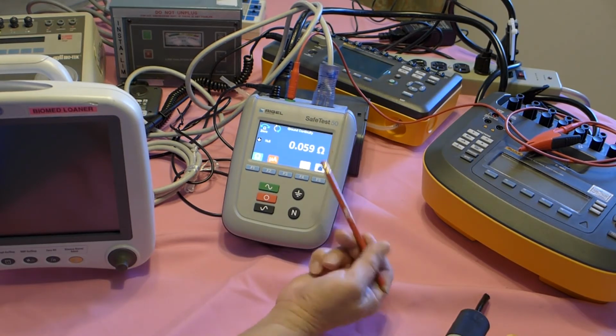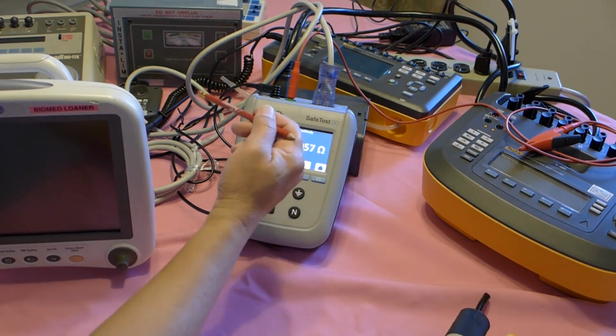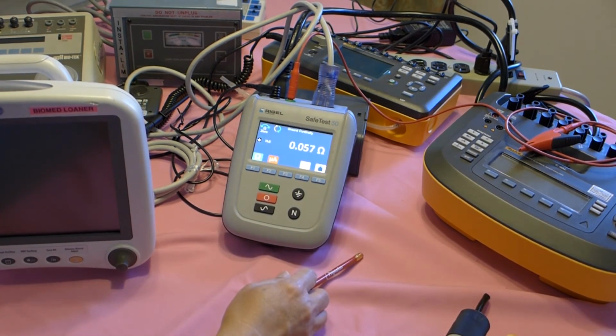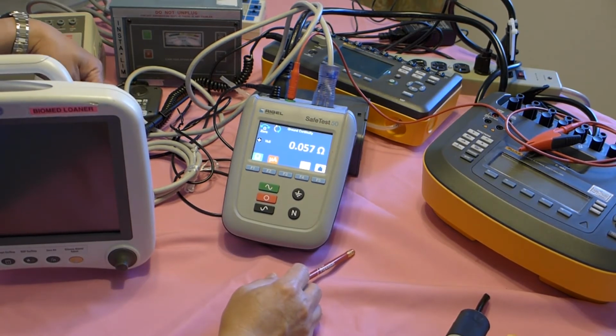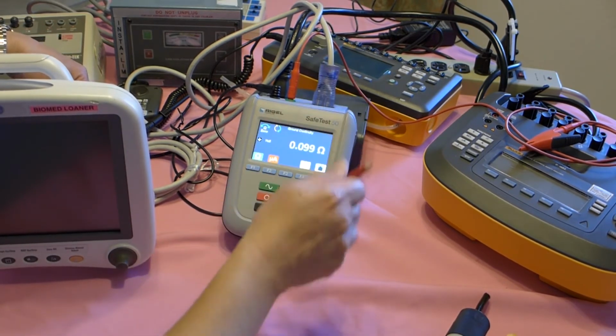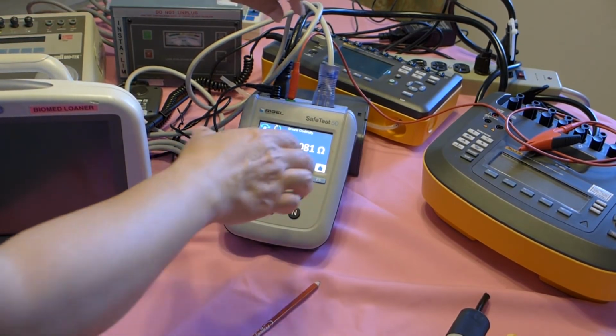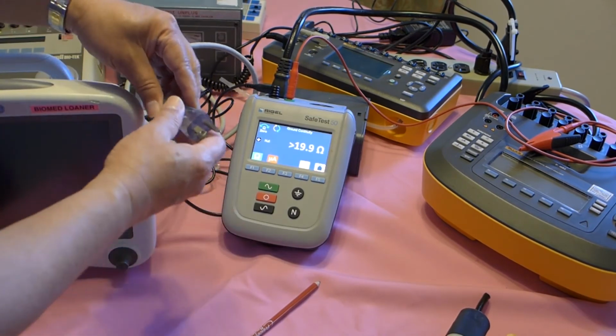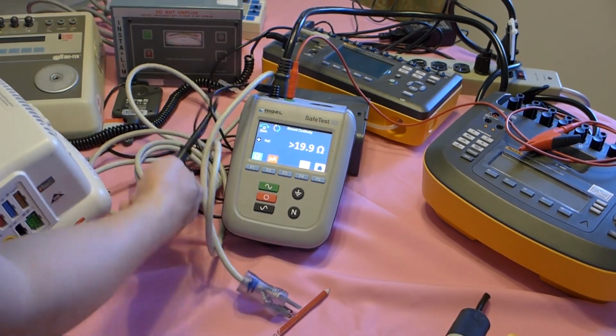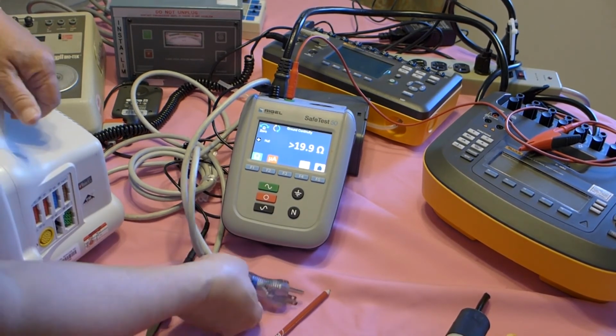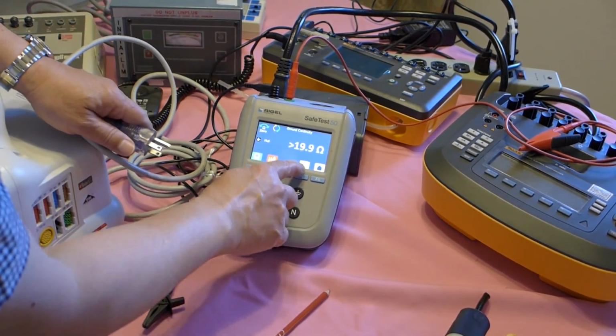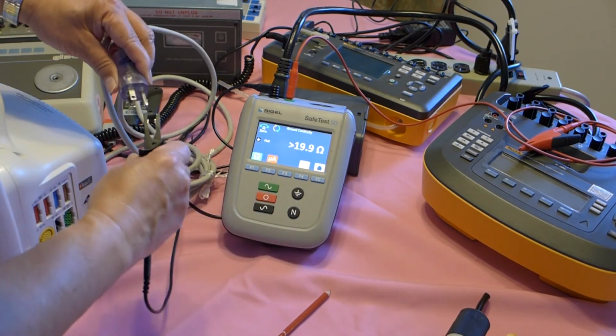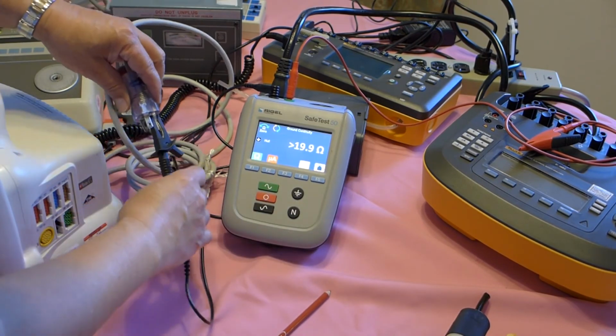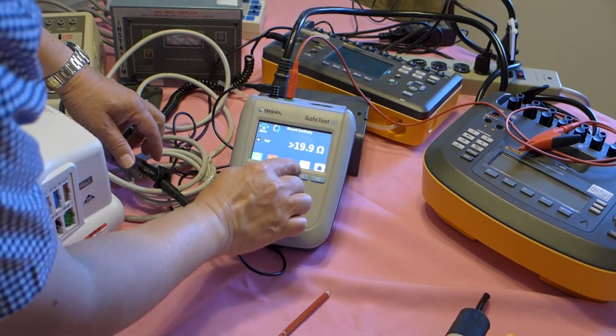Alright, let's go back to the ground wire resistance. That's pretty much we're getting from the ground wire resistance, okay, from the prongs to the tip of this power cord. So let's see, if you cannot get that, if the equipment doesn't have this prong here, what we do is we're going to select point-to-point reading here. What we should do is one of them is going to go clamp over here, and then we pick point-to-point. This means we have to use this.